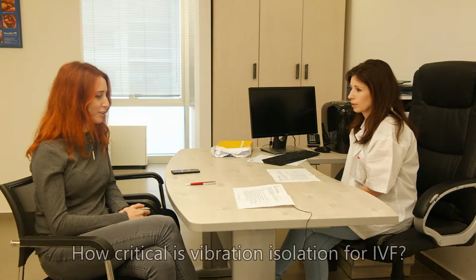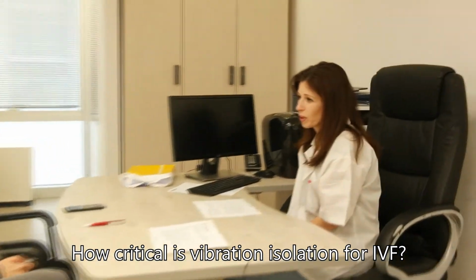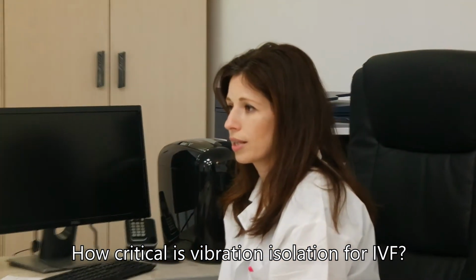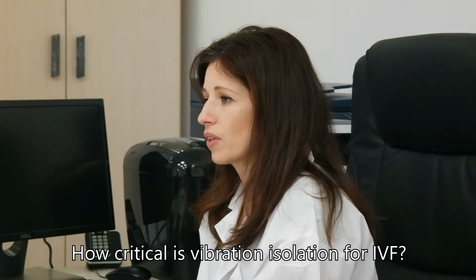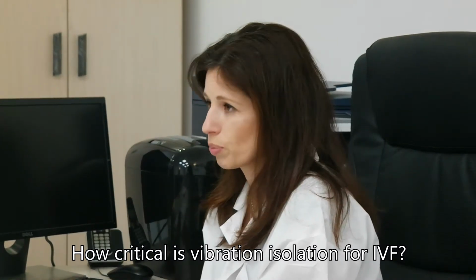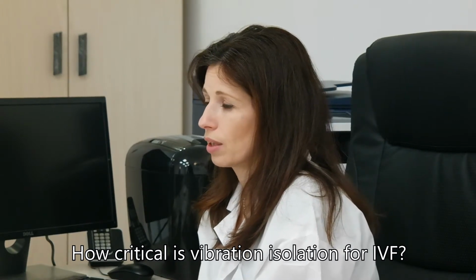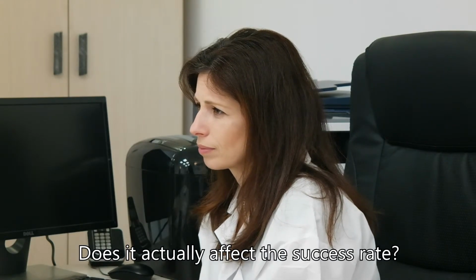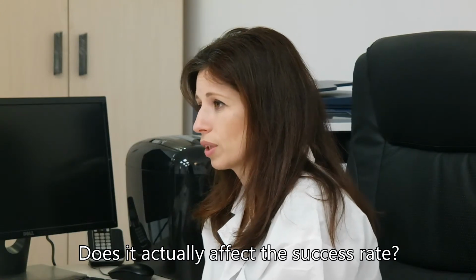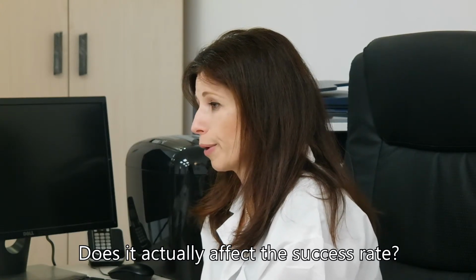How critical is vibration isolation for IVF? It's very critical because if we're fertilizing an egg and we experience a vibration in the critical phase of penetrating the sperm into the oocyte, we can damage the oocyte in such a way that it will either start degenerating, or will not result in fertilization, or will result in poor embryo quality. So actually it affects the success rate? Of course, it affects the whole process, the quality of the embryo, the success rate, and the whole process is influenced by vibration, and how to eliminate the vibration during the process.